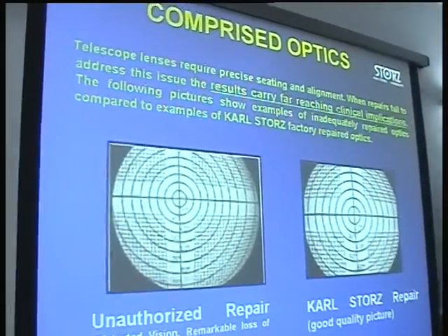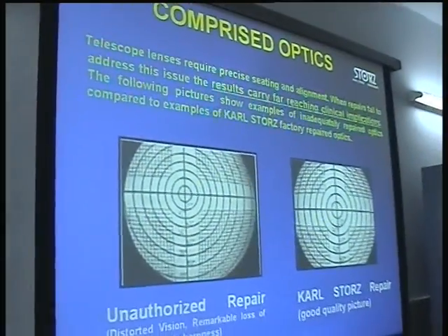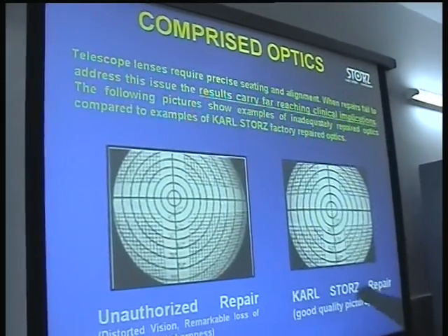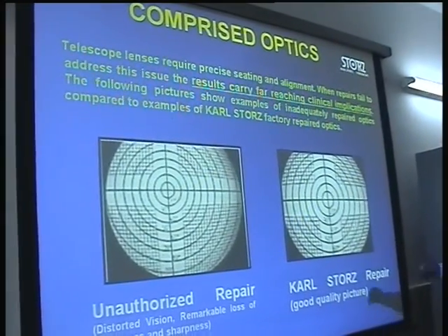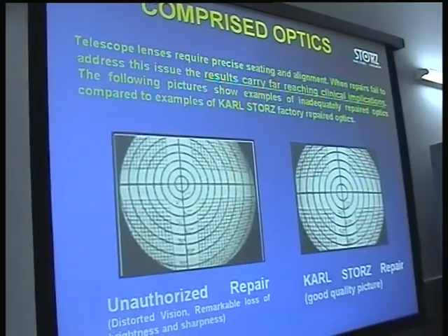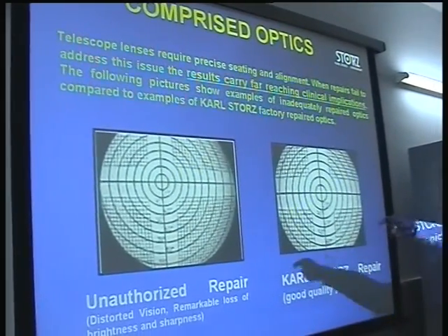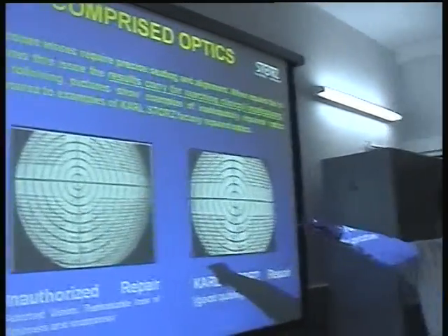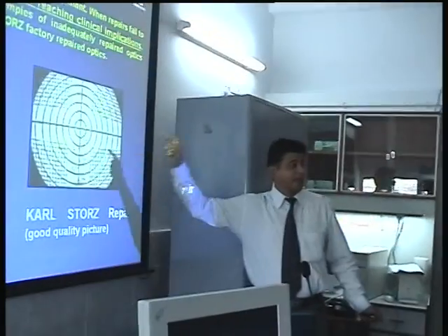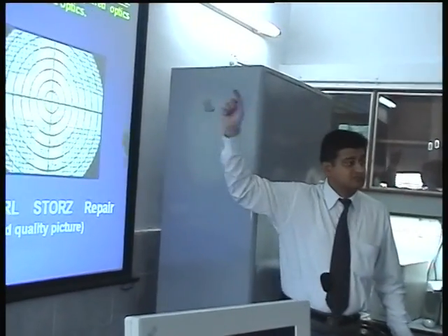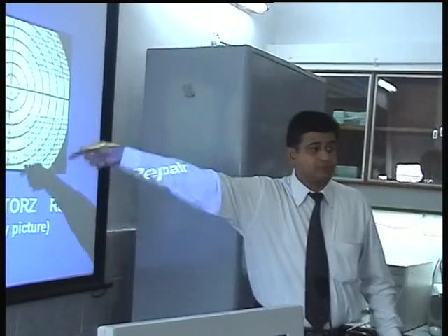Now sometimes the telescope goes bad, and then we have a tendency to give it to unauthorized stations for the repairs because we are in a hurry. And when the optics comes back after the repairs, you will find that there is a problem in the eccentricity of the alignment. Like you can see over here, the optics is not really up to the mark compared to once you do and calibrate.